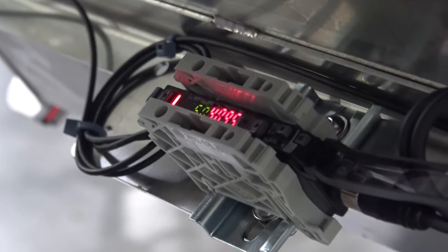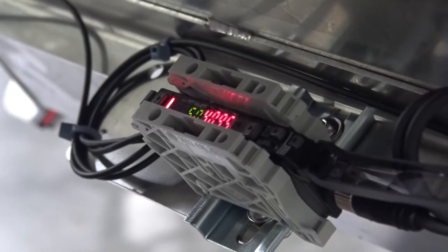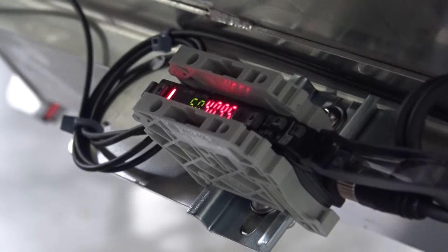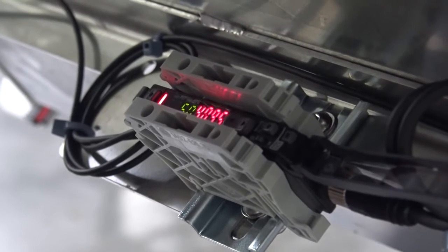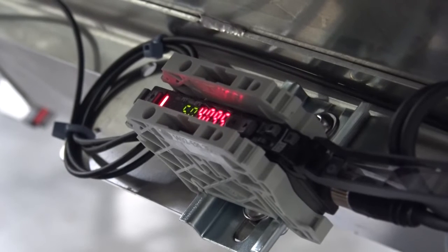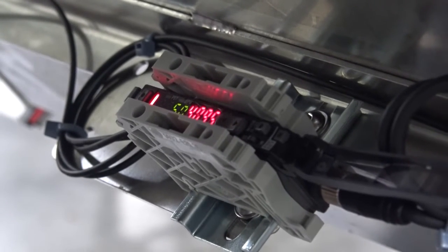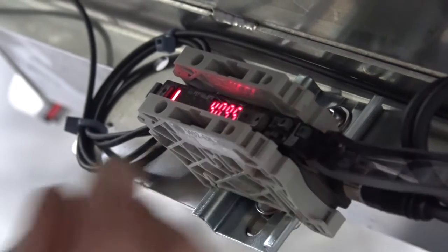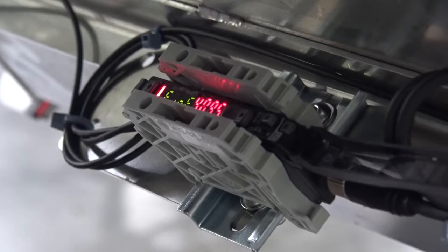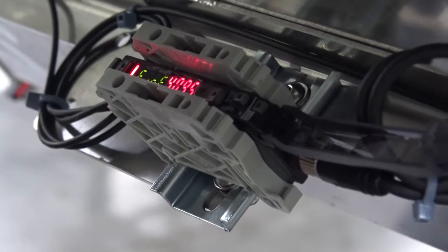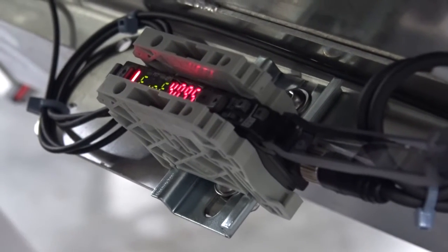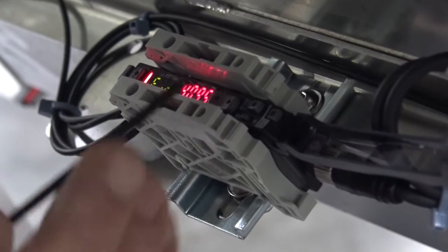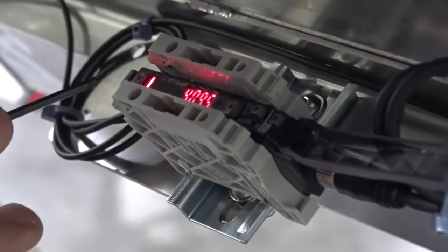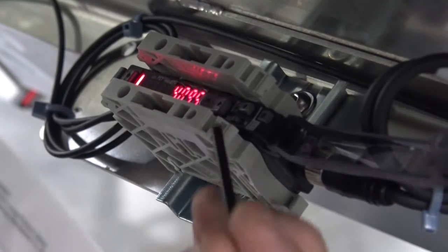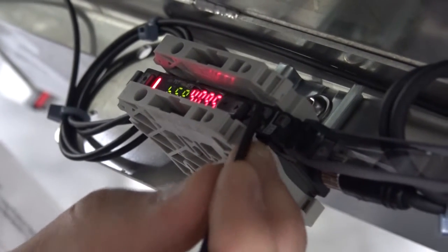Next in this application for French fries, we're going to set high speed mode. And in order to do that, we're going to press and hold mode for 3 seconds. Again, this is section B in the setup procedure. So I press and hold mode, and now I have fine blinking. For this application, we're going to set high speed mode. So I'm going to use my left-right directionals. There's HSP high speed mode. I want that. I'm going to push mode to enter.